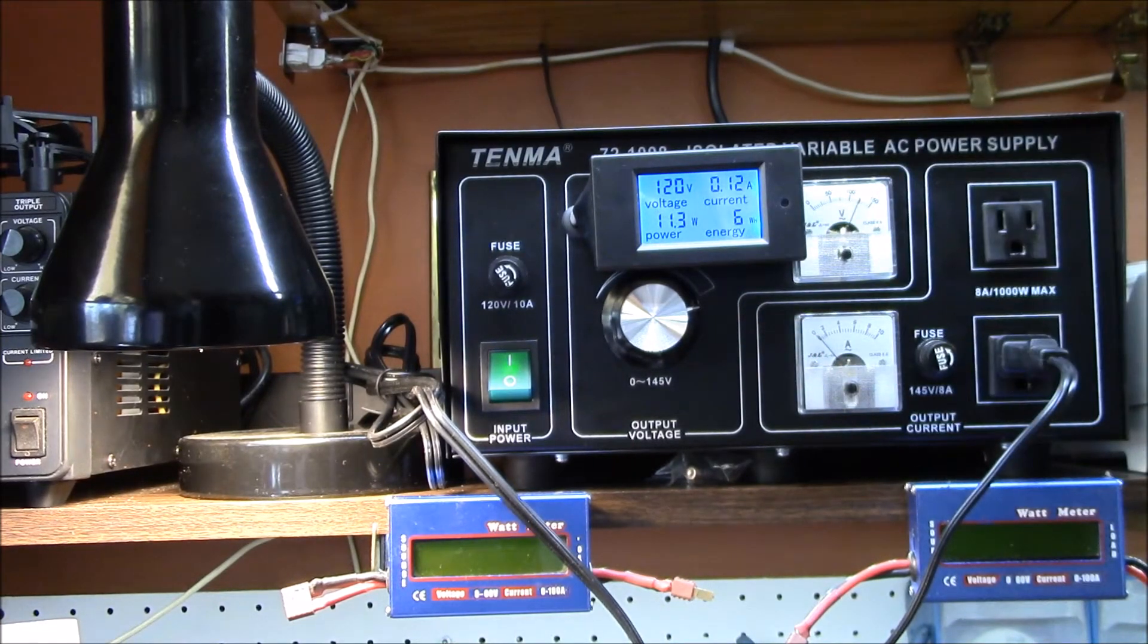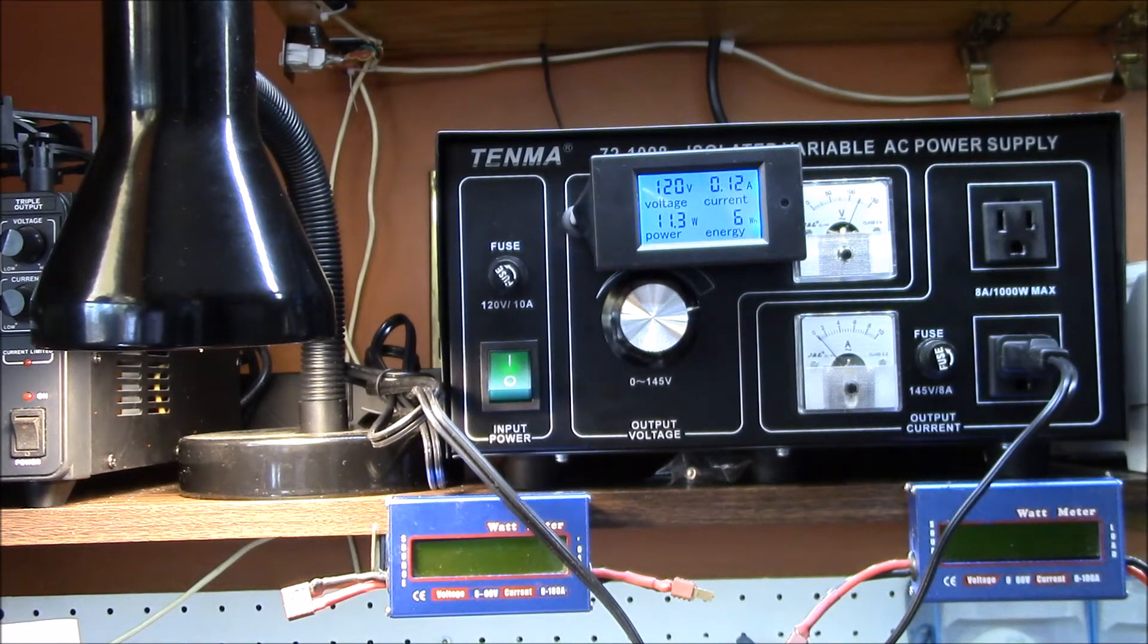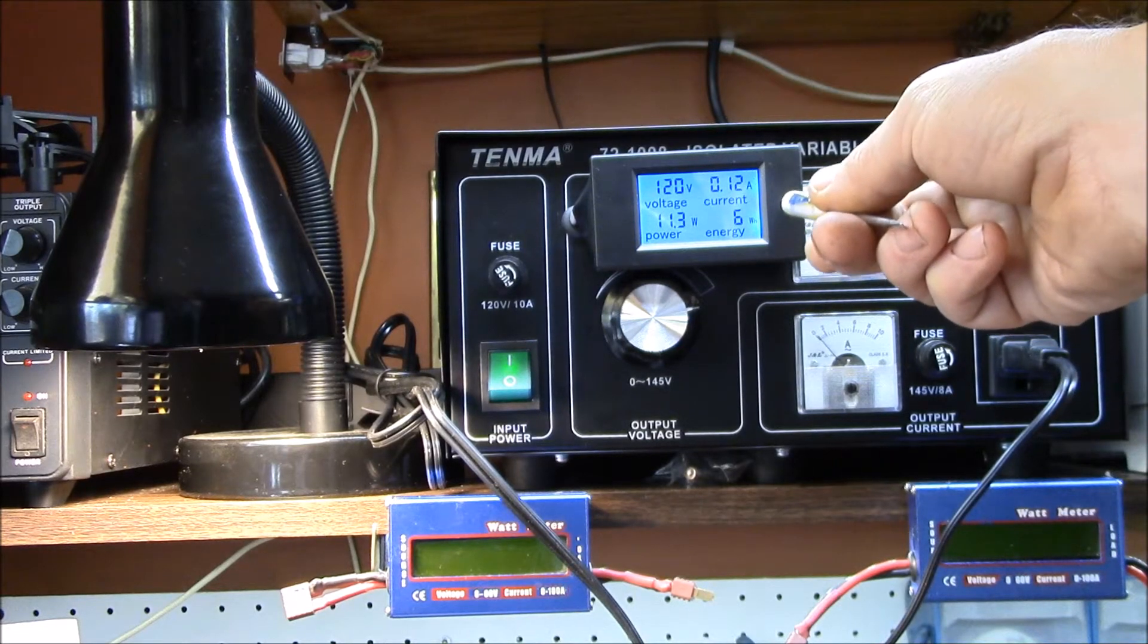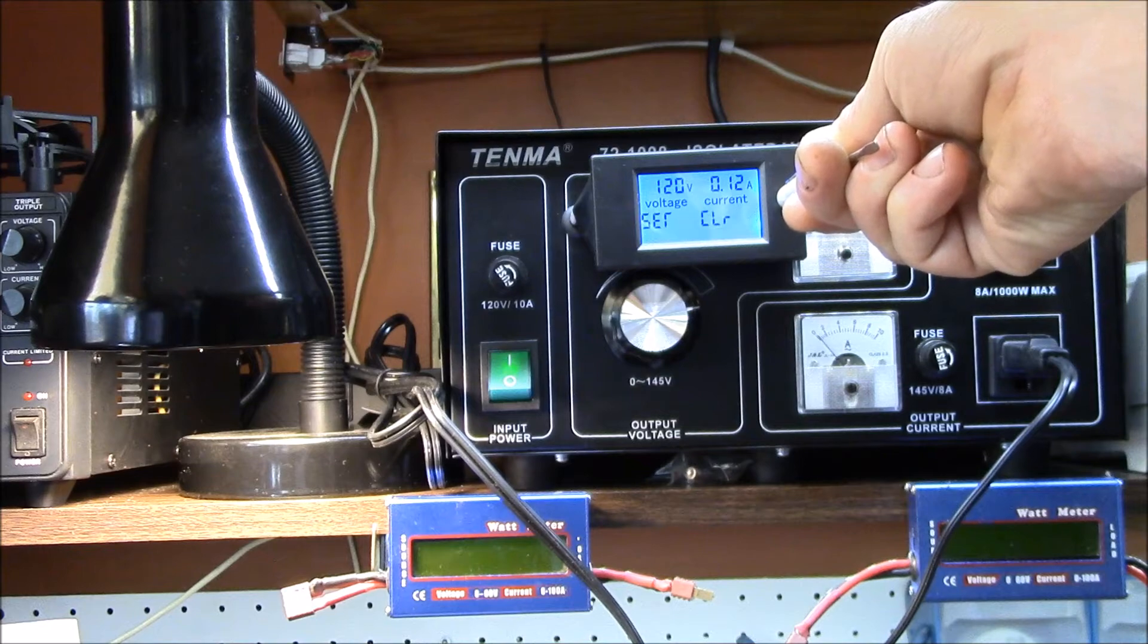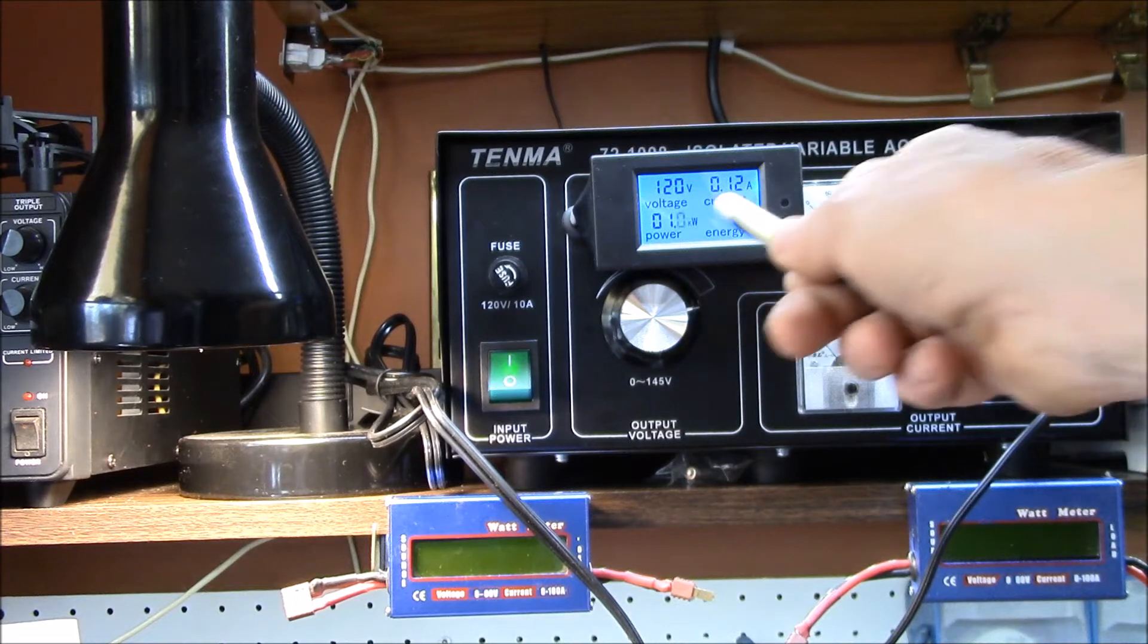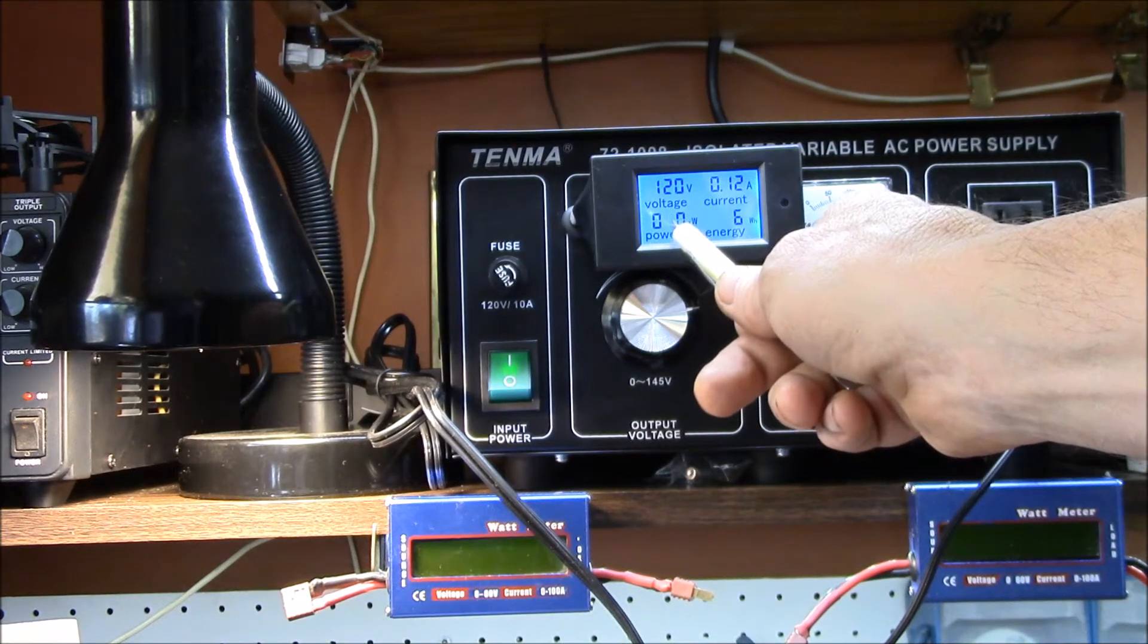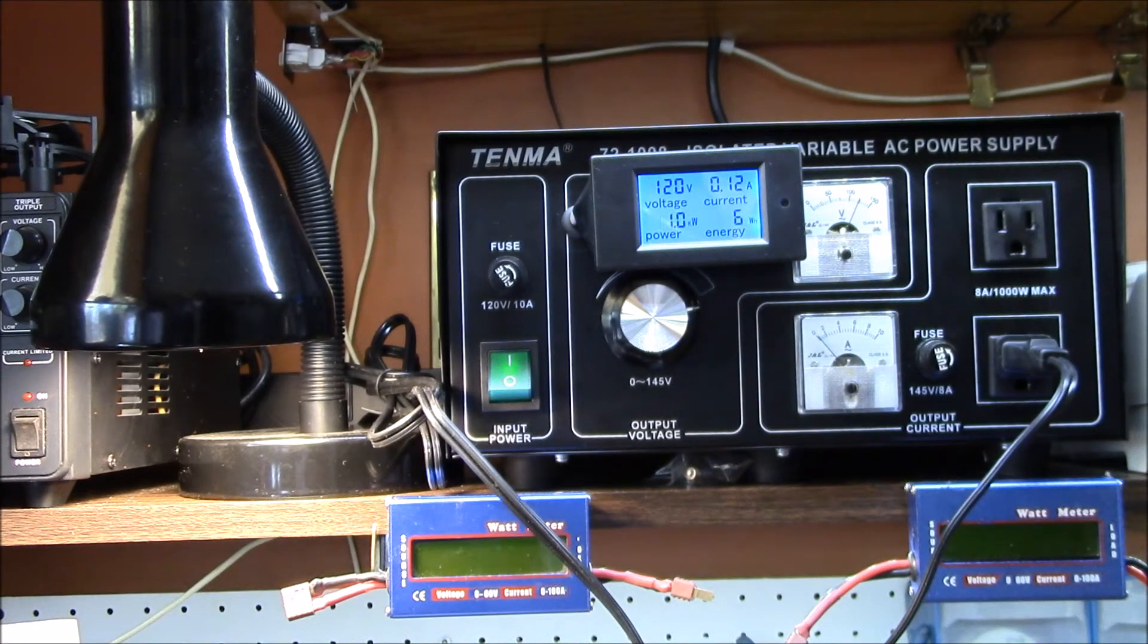There's also another feature in this device: a power limit alarm that you can set. The way you get to that is you hold the button down for five seconds and you can see it said 'set CLR'. Right now you can see it's flashing here. The default here is 22.0 kilowatts.